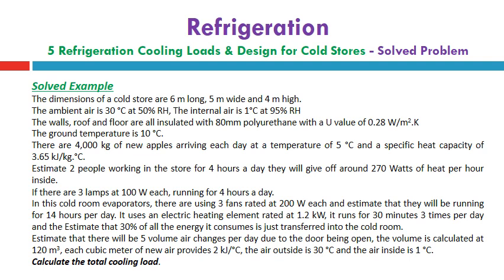In the cold room evaporators, there are 3 fans rated at 200 watt each, and we estimate that they will be running for 14 hours per day. It uses an electrical heating element rated at 1.2 kilowatt. It turns on for 30 minutes 3 times per day, and we estimate that 30% of the energy it consumes is transferred into the cold room only. Estimate also that there will be 5 volume air changes per day due to the door being opened. The volume is calculated at 120 meter cube. Each cubic meter of new air provides 2 kilojoule per degree Celsius. The air outside is 30 degrees Celsius and the air inside is 1 degree Celsius.